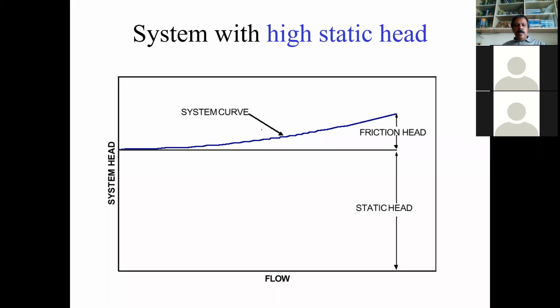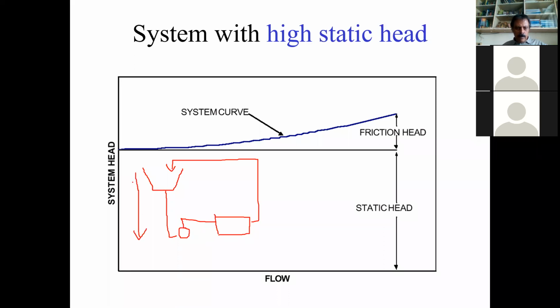But normally in a typical industrial situation, you will find that there is a little bit of static head as well as friction head. Take a cooling tower system, for example, as we have seen. Then you will have a pump. The water comes to the pump, and the pump is pumping to the various processes here. Then the return water is coming back to the top of the cooling tower. This is a case where there is some static head, which is the vertical lift in the cooling tower. Then the friction drop across these pipelines and heat exchangers all constitute the frictional component of the pressure drop. So this is a case with some static head and some frictional head.